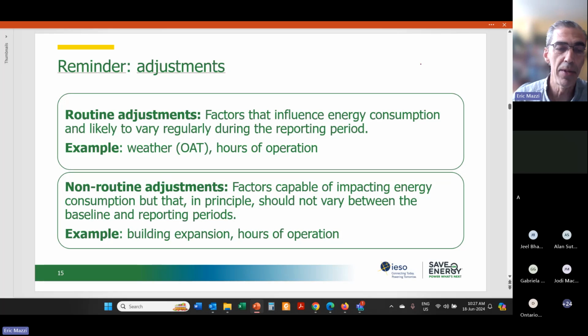But in real world projects, we don't have that ability. You cannot operate a building and dictate what the outdoor air temperature is. It's going to change, and that will affect your HVAC energy. So adjustments need to be made in order to account for those changes in variables that do affect energy consumption.